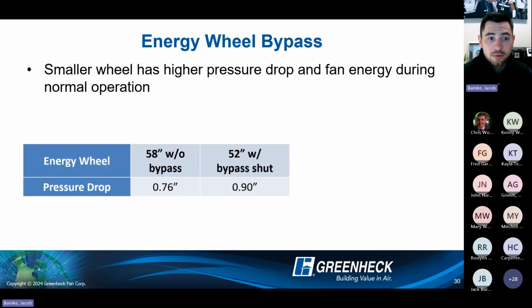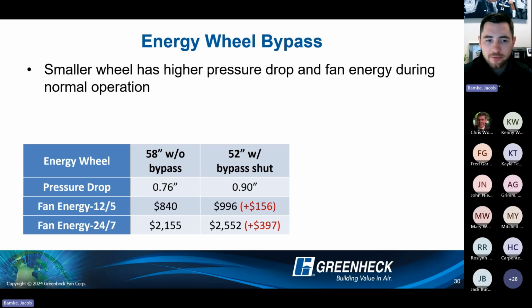So a couple things to note. When you look at just the energy wheel, the larger energy wheel has a lower pressure drop in normal operation, right? So the whole idea of using bypass dampers during economizer is to avoid the pressure drop of sending that free cooling air through the energy recovery device. On the contrary, you actually raise it during normal operation. So you look at the fan energy, if you're 5 days a week, 12 hours per day, or 24/7 type operation, this is just fan energy.